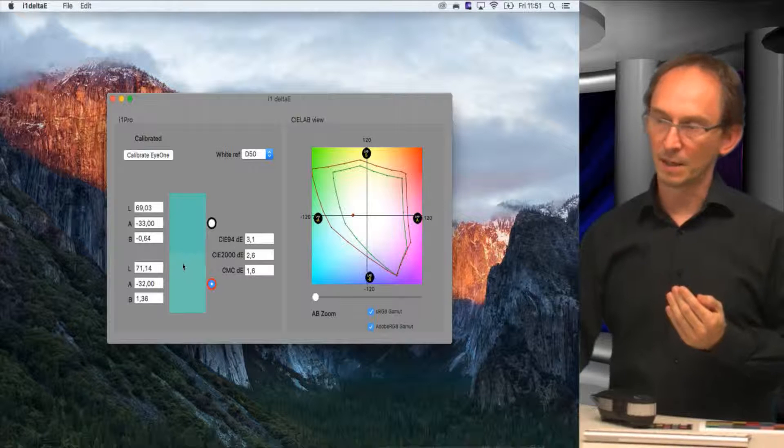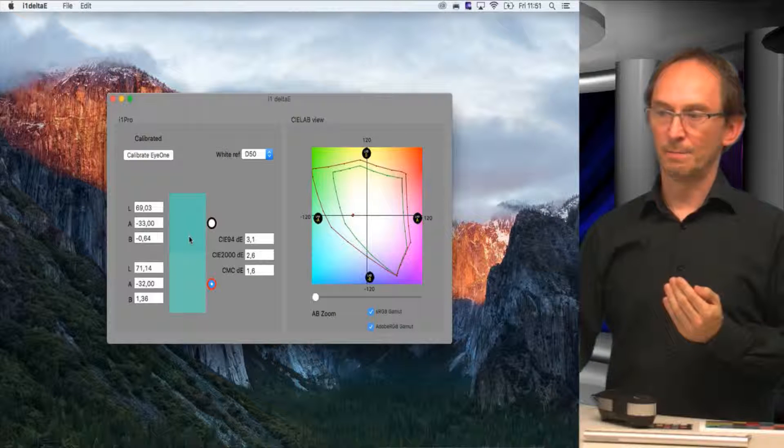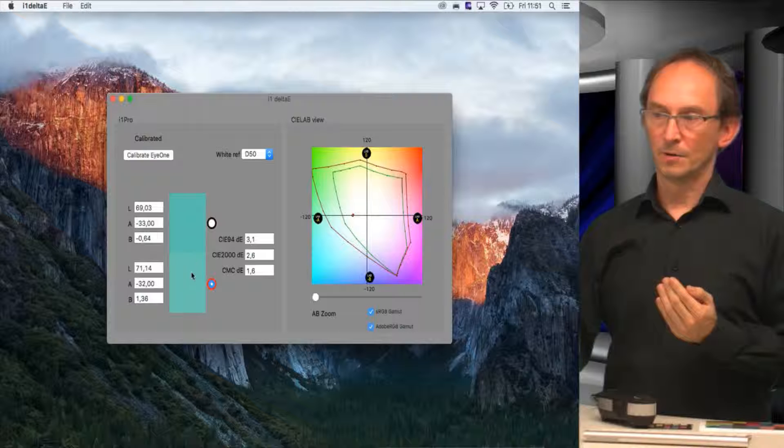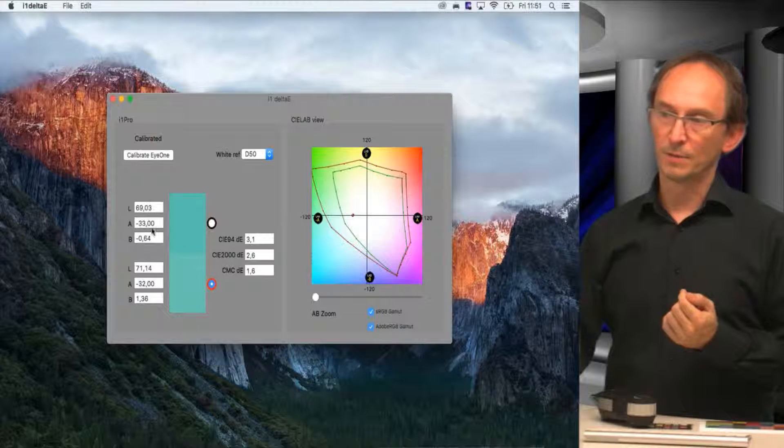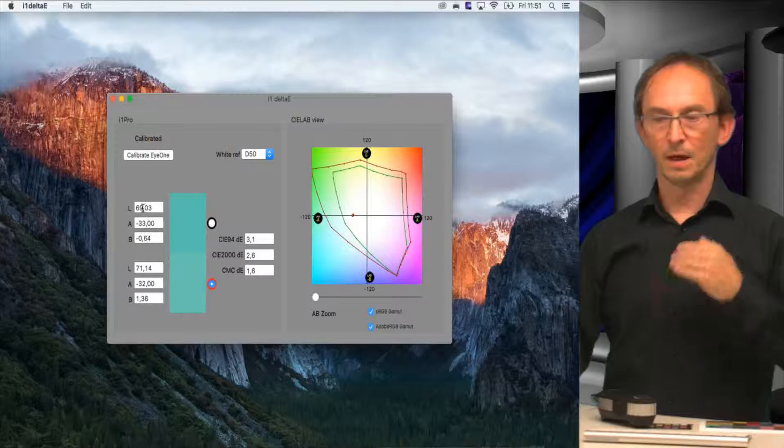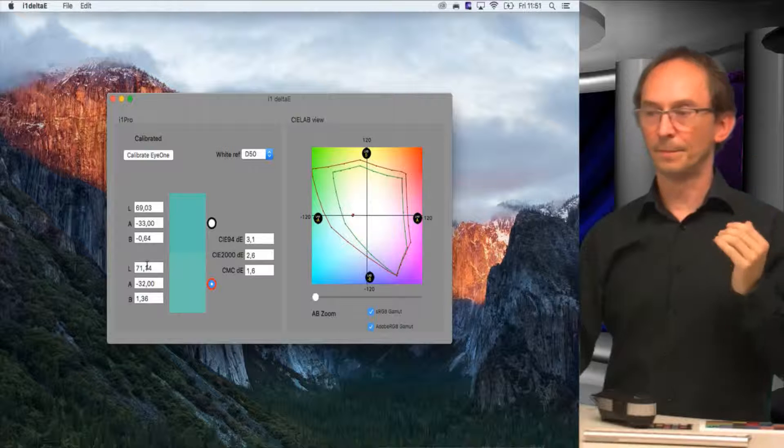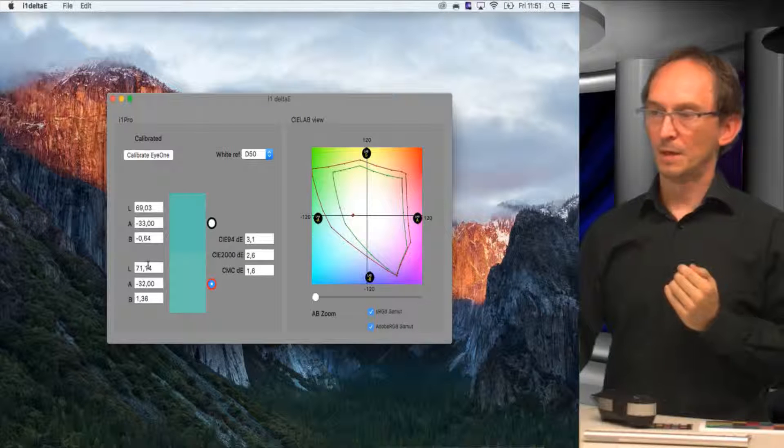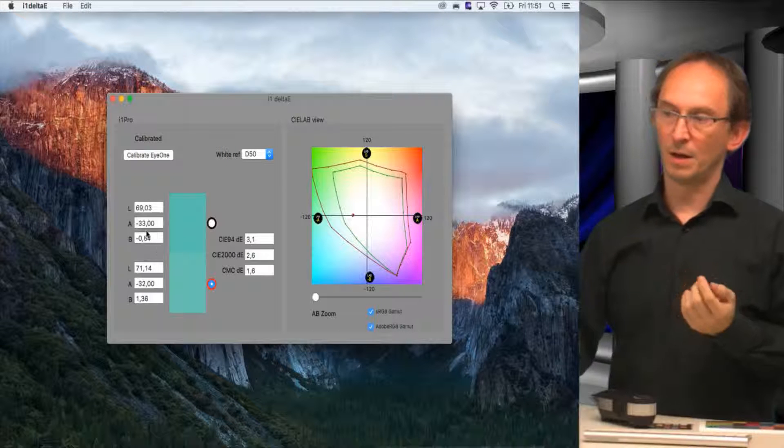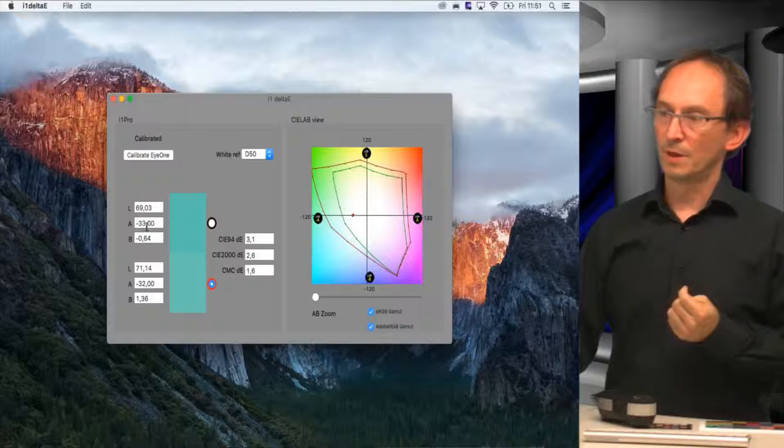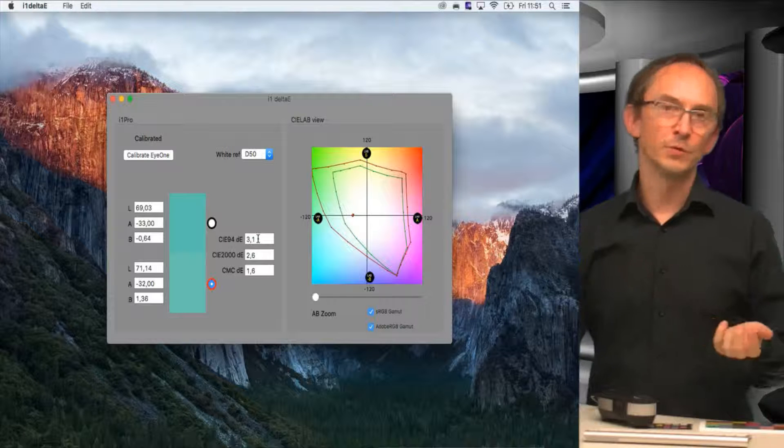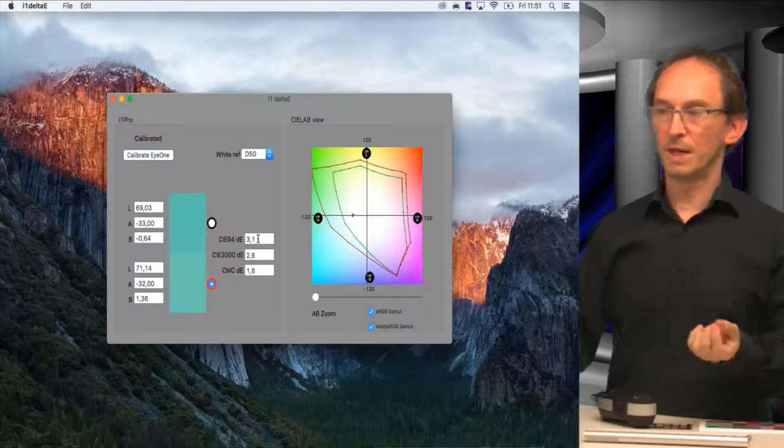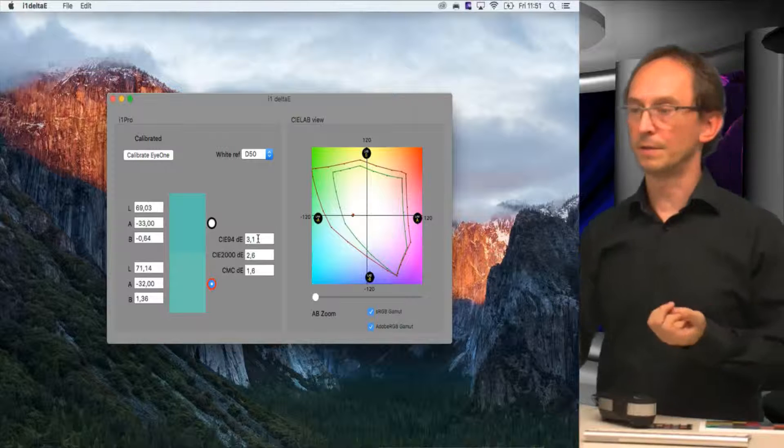You can see that this one is slightly darker than that one. You can also tell by the L value. This is lower than that one. The higher L value gives you a lighter color. It's also off a little bit, not a lot, but in total it's off by 3.1 according to the mostly used CIE 94 standard.